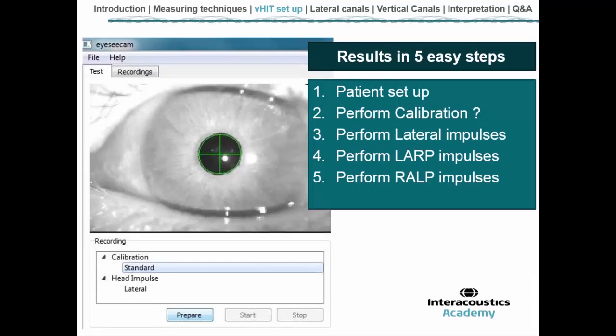So let's talk about the measurement process. How do we actually record and perform the video head impulse test? What I'm going to do today is focus my attention on the diagnostic video head impulse test. There's two ways in which you can use the EyeSeeCam. The first is to perform a screening test where you don't do any calibration, you just put the goggle on and perform lateral canal impulses and then look at the results. The second is where we do a full diagnostic test where we're going to do a calibration to assess all 6 semicircular canals.